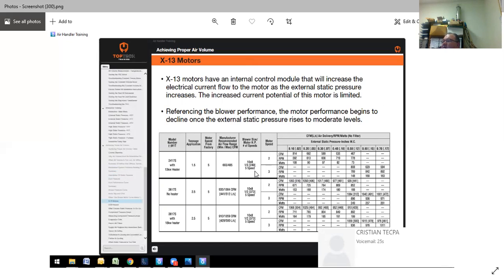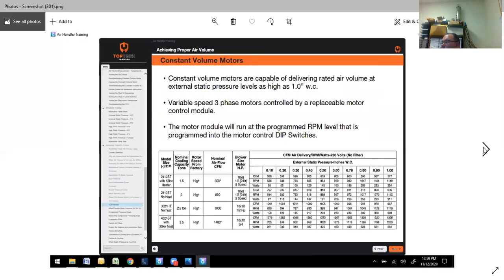So in this case, the 5-speed motor, we will go to speed tap 3. At 0.5, we're actually at 808. If we go to 0.70, we're at 584. Now, if we increase that up to 0.9, you can just see it's going to keep on reducing. Not only is it going to reduce, but it's also going to cost your customer more money. And chances are it's going to be significantly louder right out of the box because of that high static pressure.